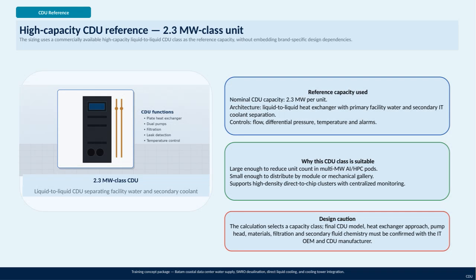Here, we're focusing on the CDU reference, specifically a high-capacity 2.3 megawatt class unit. This capacity was chosen because it corresponds to a commercially available liquid-to-liquid CDU class, which means we're not tied to any particular brand or proprietary design. This makes the sizing more flexible and practical for a wide range of applications. The training concept package ties together multiple components. It includes a Batam coastal data center's water supply, seawater reverse osmosis desalination, direct liquid cooling, and integration with the cooling tower. All these elements come together to create an optimized cooling strategy.